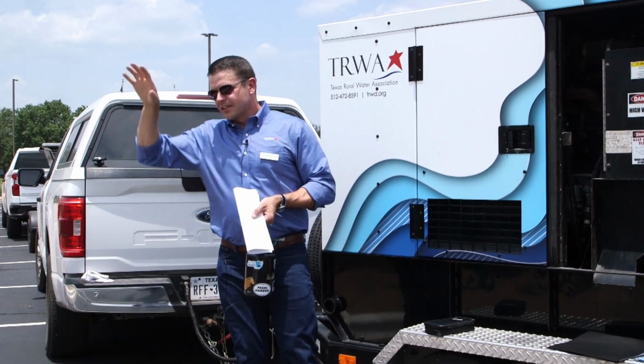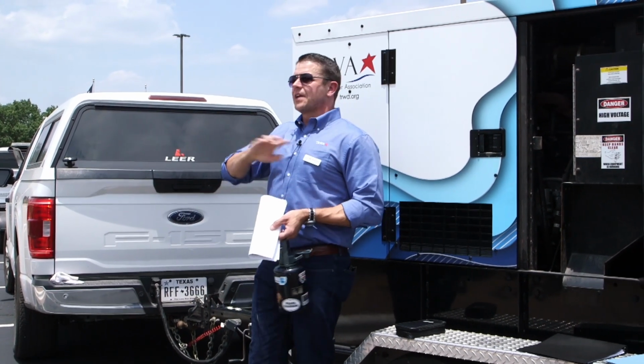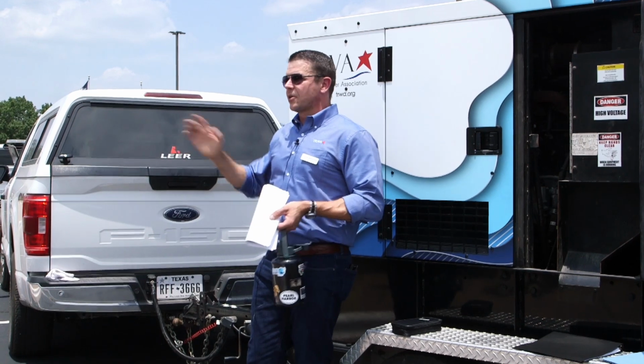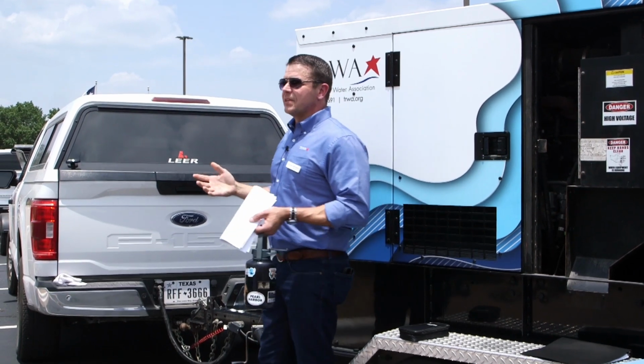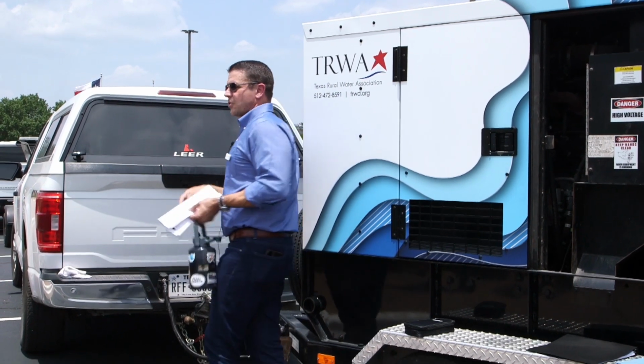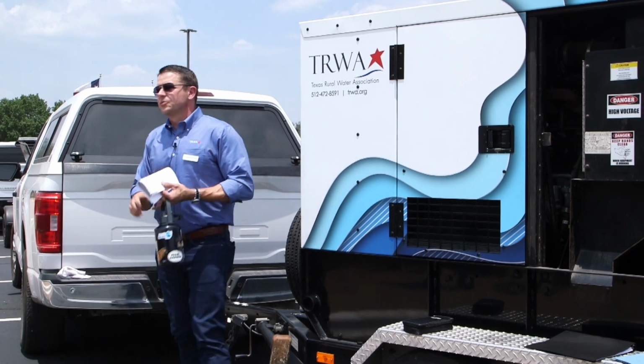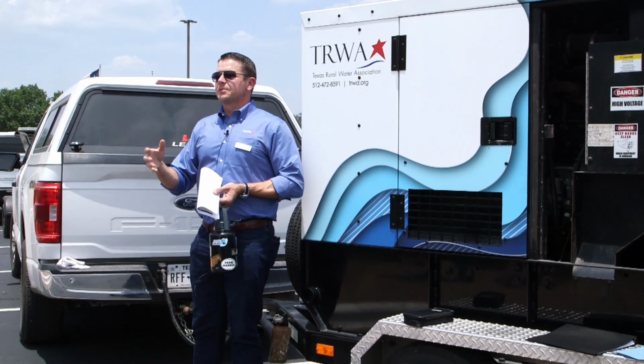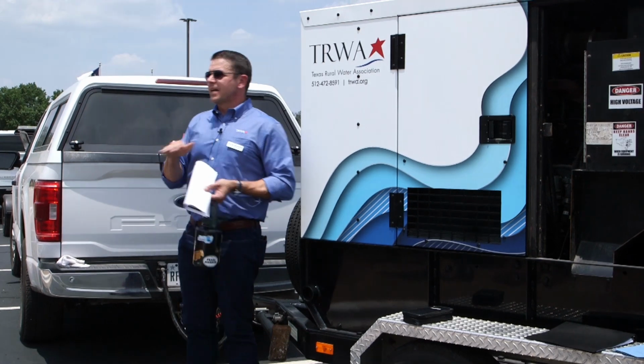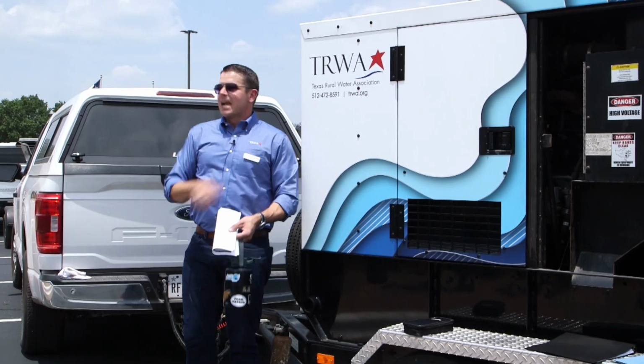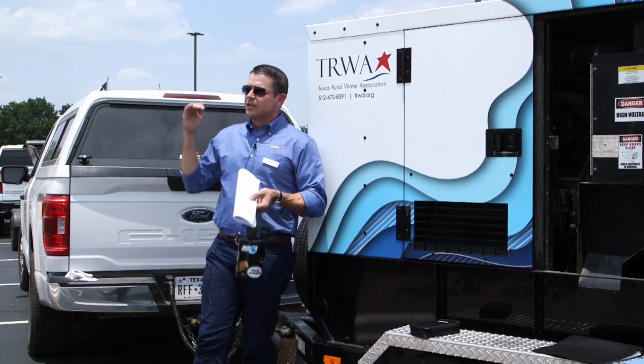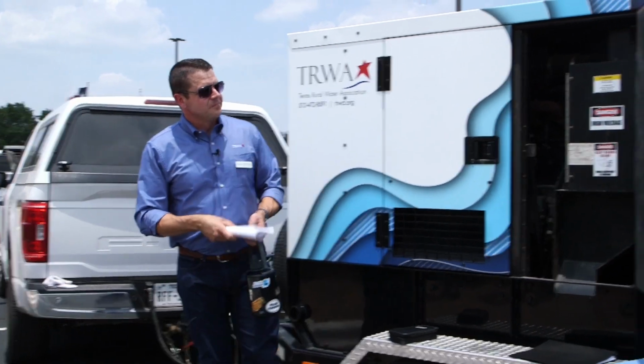So check that first, and make sure all the applications are off. Typically when the power goes off, things were running, meaning they're still being called for, whether by turn controls or pressure switches or whatever calls for those pumps. It's better to start with a blank application, since as soon as you turn the power on, everything doesn't kick on at once, so make sure everything is off.